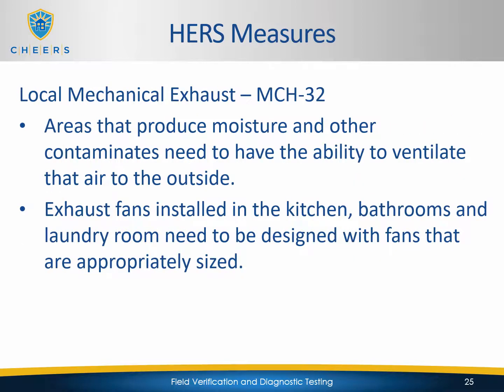Local mechanical exhaust is MCH-32. We already talked about the whole home ventilation systems, so this kind of goes along with that, but this is local. This is for areas that produce moisture and other contaminants. They need to have the ability to ventilate that to the outside. So exhaust fans will be installed in the kitchen, bathrooms, and laundry room, and these need to be designed with fans that are appropriately sized.